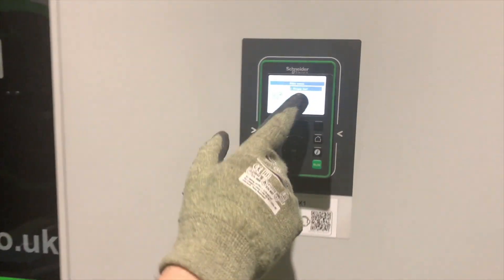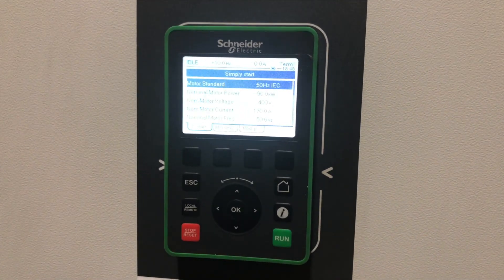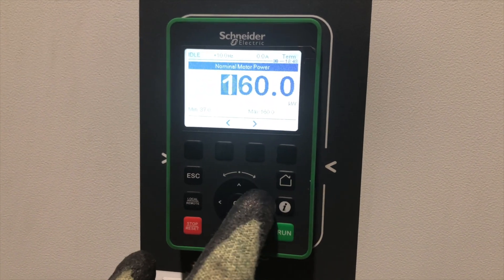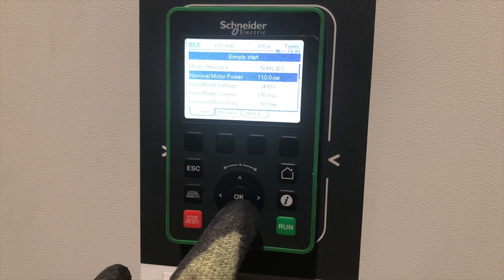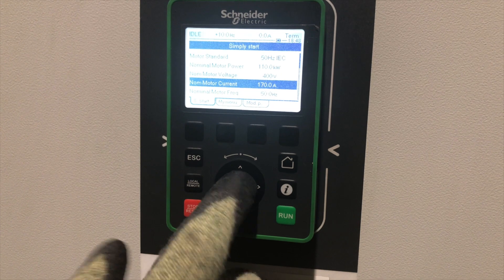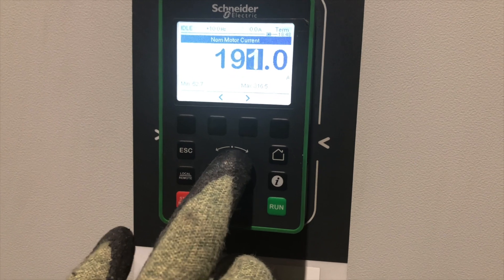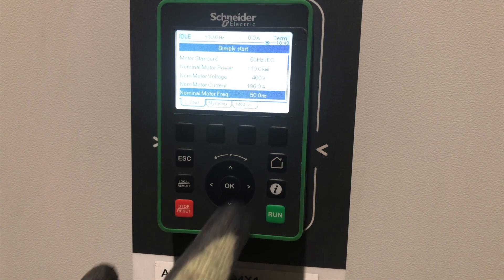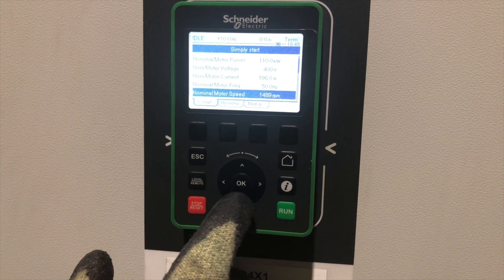In this instance we can simply go for a simple start because we're only changing the basic parameters. We input the correct details: this is a 110 kilowatt motor, the nominal motor voltage is 400 volts, the motor nominal current is 196 amps, our frequency is 50 hertz, and our motor nominal speed is 1489 RPM.